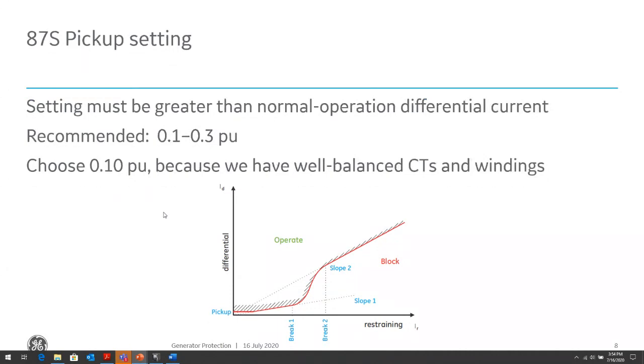And then your pickup setting should be set such that it will handle any type of standing differential that the relay will be calculating during normal operation. And why would you see standing differential during normal operation? A couple of things. One, CT inaccuracy. At worst, relay class CTs are only required to be 10% accurate. That's a lot of inaccuracy there. You can get CTs that are better than that, obviously, but the standards at minimum require a 10% accuracy for relay class CTs.